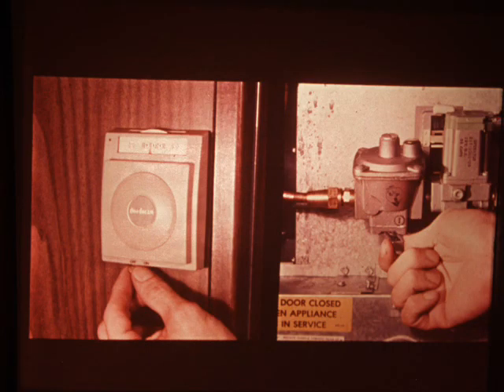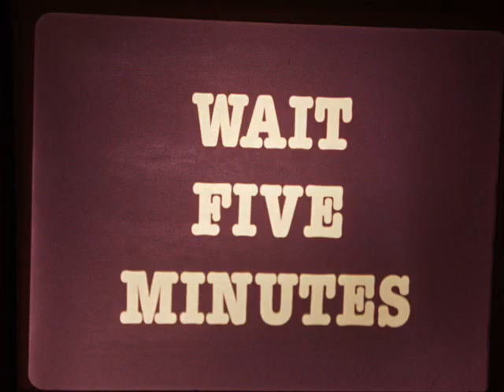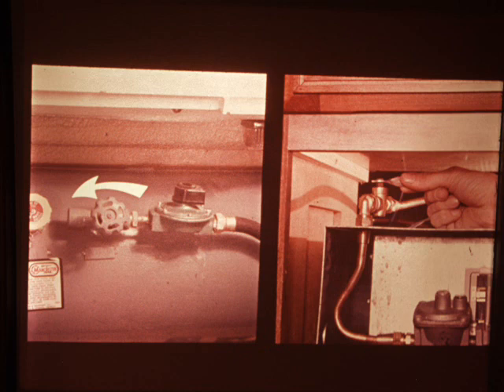First, turn the thermostat and furnace gas valve off. Wait 5 minutes for any LP gas fumes in the combustion chamber to dissipate. Now, check that the valve on the LP supply tank and the manual valve on top of the furnace are fully open.